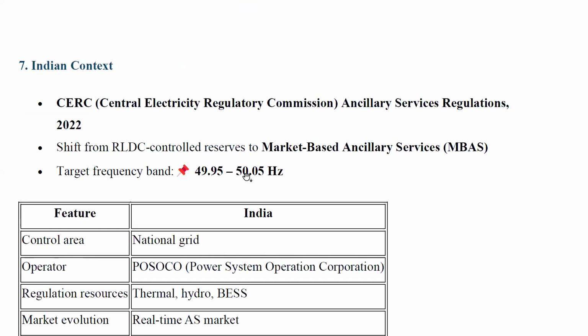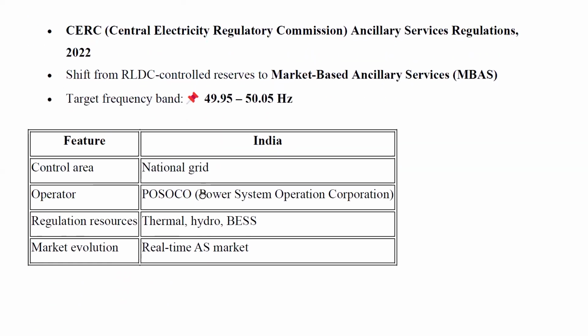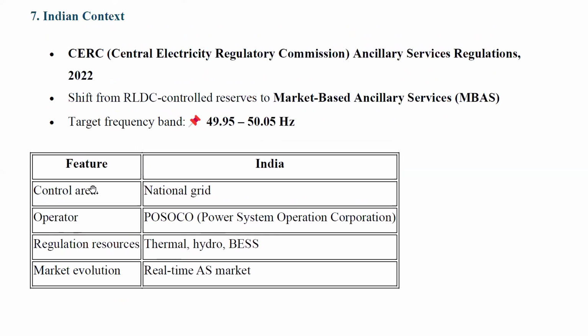In the Indian context, the Central Electricity Regulatory Commission is there. This is also one of the ancillary services, with regulation under 2022. Here the main shift is from regional dispatch center control to market-based ancillary services in the Indian context. The target frequency band is 49.95 hertz to 50.05 hertz. In India, the control area, the National Grid, is maintained by POSOCO, that means Power System Operation Corporation.